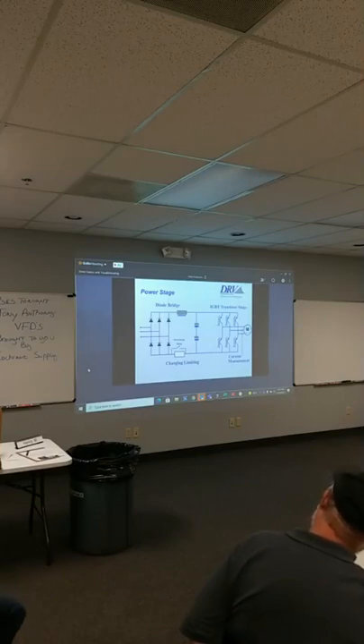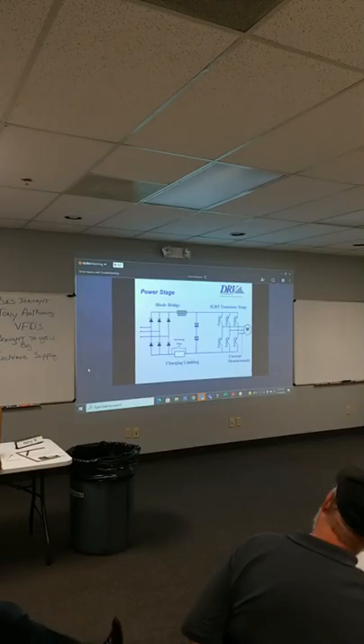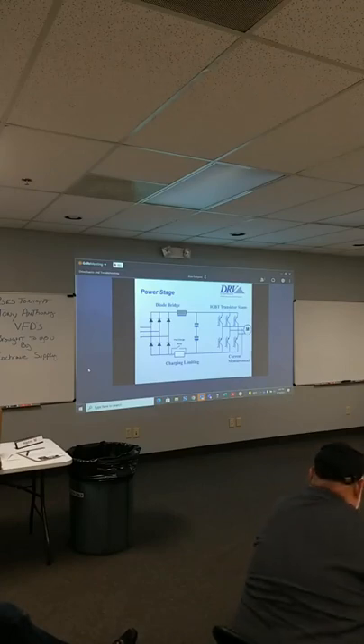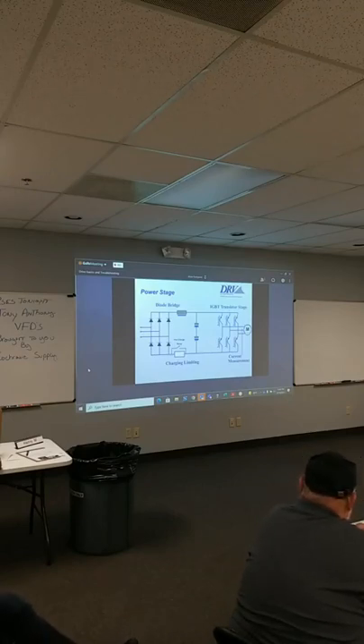I'm going to back up to that main screen here a second. Remember how I told you to check the diode bridge if your DC bus was not working or didn't appear right? You could take an ohm meter and go one way and then reverse it. You can do the exact same thing on the output section. Disconnect the motor. Go from your T1 motor lead to your plus DC bus and reverse it, just like with a diode, because an IGBT is just a fancier diode. They just are even more easily controlled. That's how you can check your IGBTs to find out if you got a bad IGBT or not. Take an ohm meter to T1 to plus, reverse it. One way should be a short, one way should be open. Do the same for all three, T1, T2, and T3, and then do the same thing to the negative bus. T1 to the negative bus, reverse it. That way you can check all your IGBTs, and that's a simple way to see if you have a bad IGBT on the output of the drive.